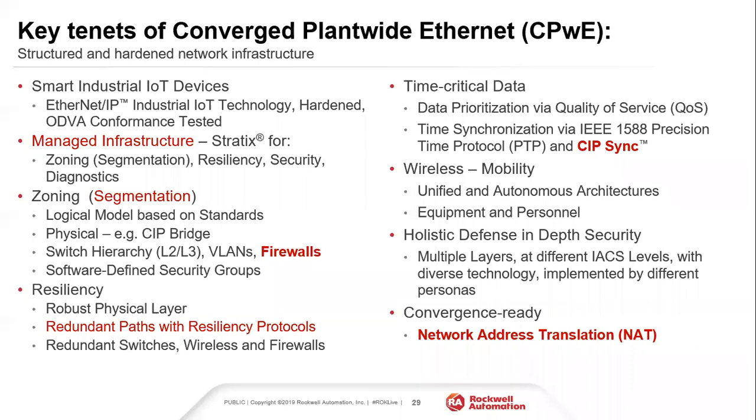If you have a piece of equipment that you're getting into your facility and you don't want to change the IP addresses, but you want it to match the IP address scheme that you have on your network, one of the options is to put a network address translation box in front of it. There's a little table, similar to what I was talking about with that device, DHCP. You can set up a table that says this IP address looks like this IP address to the rest of the network. For an OEM putting out a process skid over and over again, the IP addresses never have to change. They put this little box, they put a table on it, and then when you tie it into your network, it all matches your address scheme, but they don't have to do anything on their end.